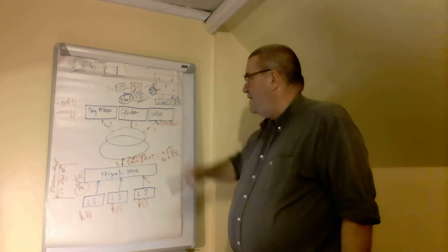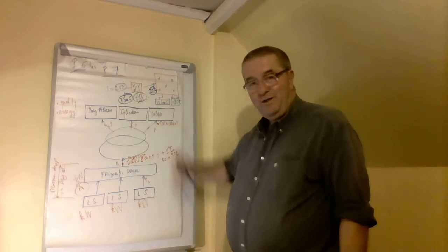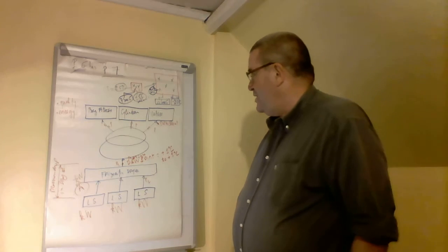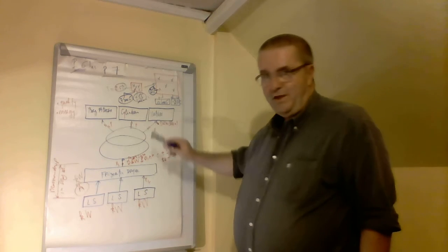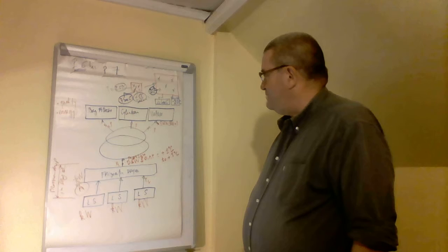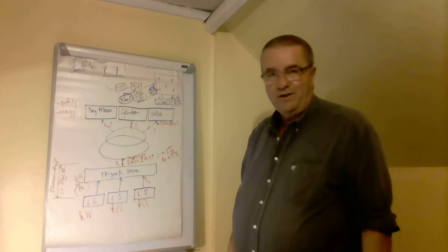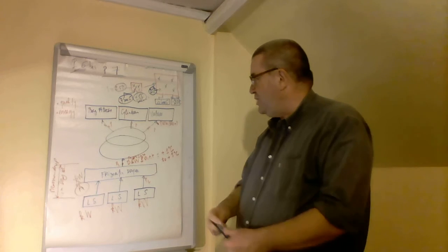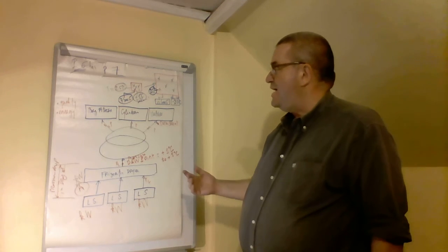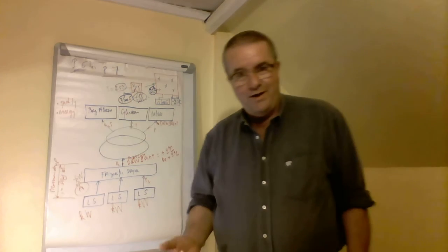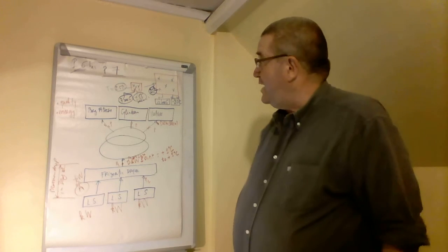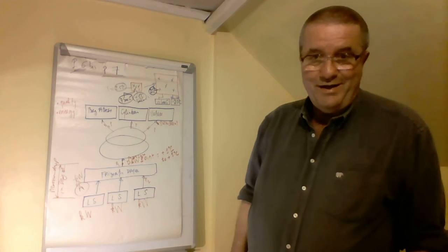And then concerning the valves, what I can tell you already is that at -20 under pressure, a much drier air would be better. What people call instrument air usually is much drier than a frigorific dryer. It's an adsorption dryer that you use locally for these valves. So we shall discuss these aspects in the next lesson, in the next course, which will be number 8. Thank you very much.